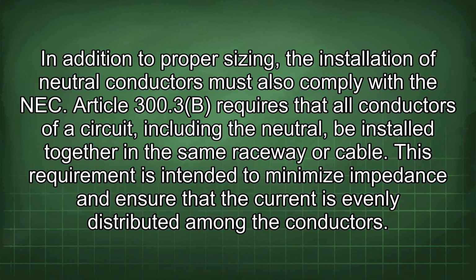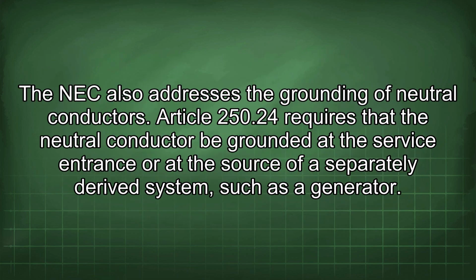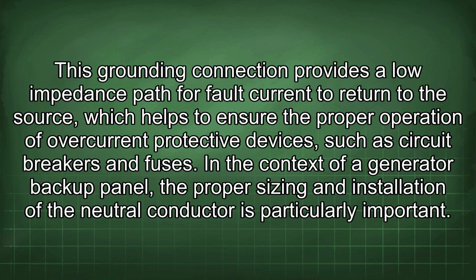In addition to proper sizing, the installation of neutral conductors must also comply with the NEC. Article 300.3(b) requires that all conductors of a circuit, including the neutral, be installed together in the same raceway or cable. This requirement is intended to minimize impedance and ensure that the current is evenly distributed among the conductors. The NEC also addresses the grounding of neutral conductors. Article 250.24 requires that the neutral conductor be grounded at the service entrance or at the source of a separately derived system such as a generator. This grounding connection provides a low impedance path for fault current to return to the source, which helps to ensure the proper operation of overcurrent protective devices such as circuit breakers and fuses.